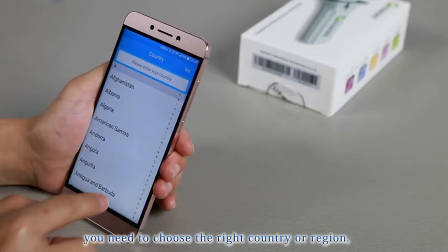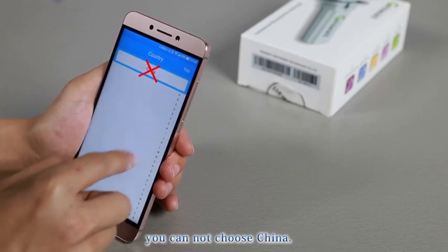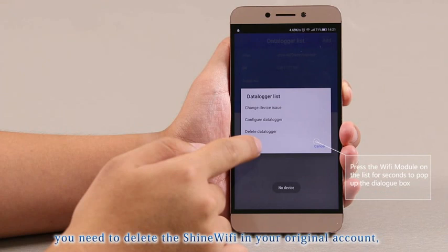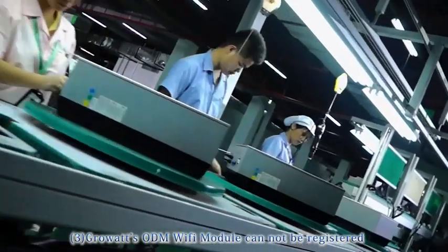Please pay attention to the following key points. (1) When registering, you need to choose the right country or region — you cannot choose China. (2) If you are trying to use another account for configuration, you need to delete the Shine Wi-Fi from your original account in order to add it to another account. (3) Growatt's ODM Wi-Fi module cannot be registered on Growatt's ShineServer for monitoring.